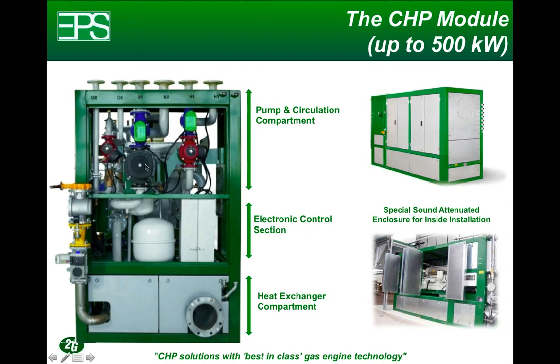Here's another pump that is used for interface with the radiator, so when the building does not utilize all the heat that is available from the cogeneration unit, this large pump here will circulate water to a nearby radiator where the cooling takes place. And then here's a smaller pump that would circulate the water for the intercooler, which often is at temperatures too low to be utilized. So you get a complete system with all the connections ready for interconnection to the building system: hot water to the building, hot water to the main radiator, hot water to the intercooler radiator, and you get a complete package system that is ready for interconnection to the building services.